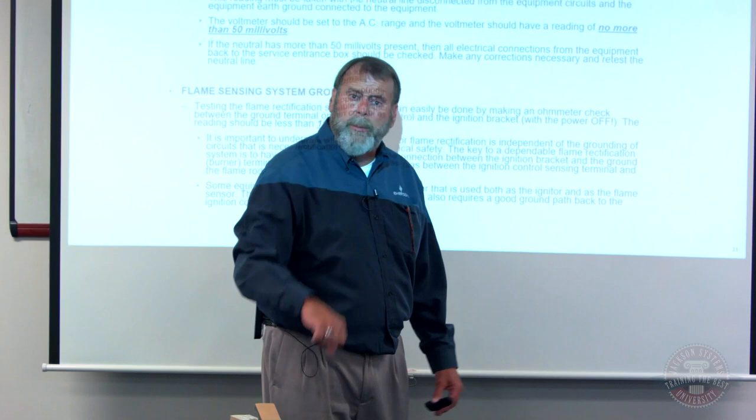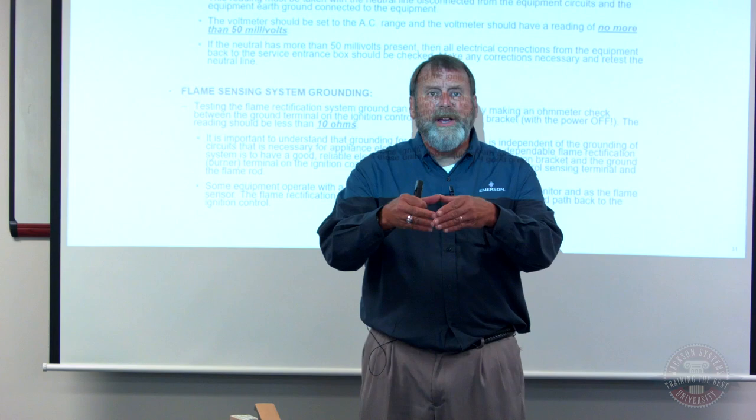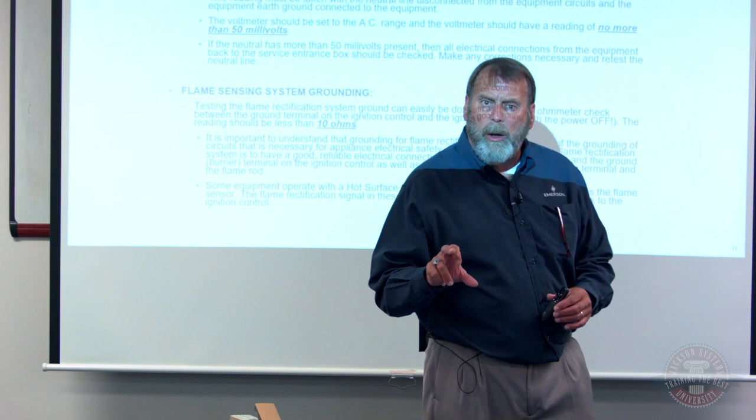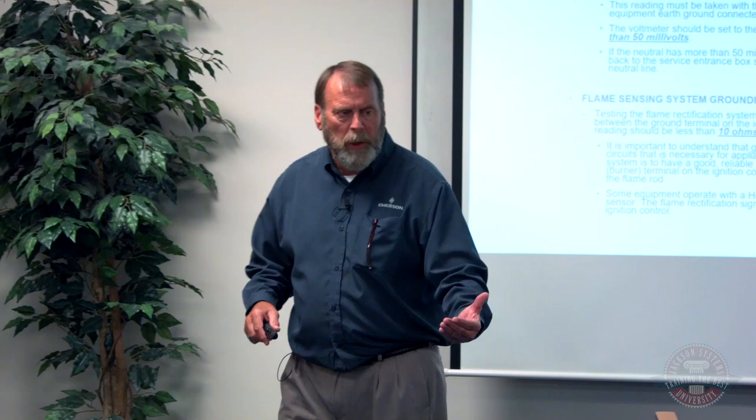When you get a drought, what happens to soil? Why did my earth start cracking when I have clay? As you dry it out, it pulls away and you get an air gap. And what was occurring was the ground rod, because they weren't properly installed, they were just barely into the ground. When it dried out, it pulled away from it and left an air gap. We didn't have a firmly bonded ground. As soon as it rained, we finally got rain in August, problems went away.